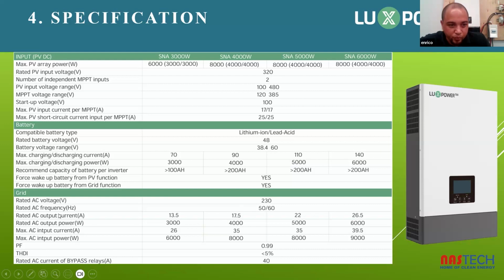maximum charging and discharging. On the grid side, we have an AC voltage of 230 volts in this particular country. Frequency 50 and 60 hertz that can be set online. The AC output of the inverter is 22 amps, and the max wattage of the inverter is, of course, 5 kilowatts AC output. The 230 multiplied by the 22 amps here will give you the 5 kilowatt output.